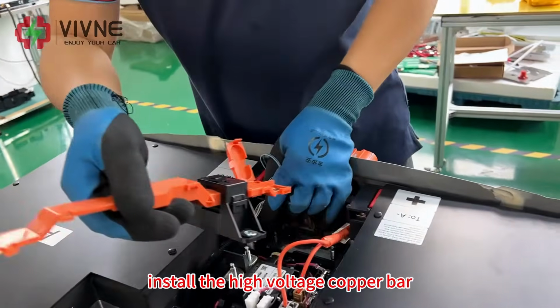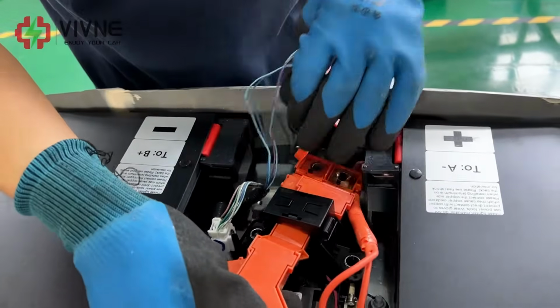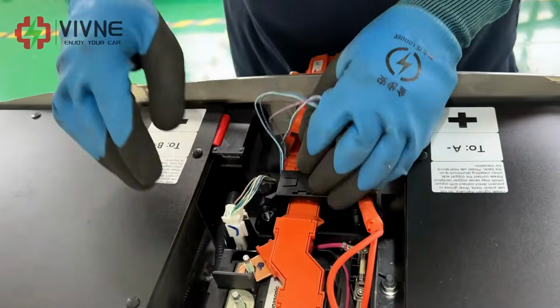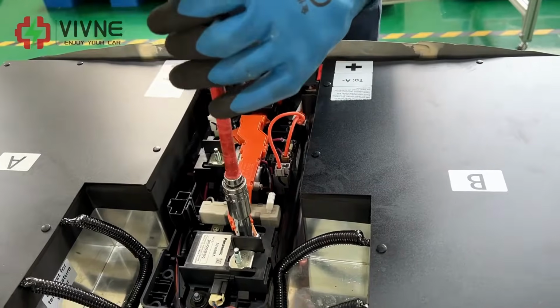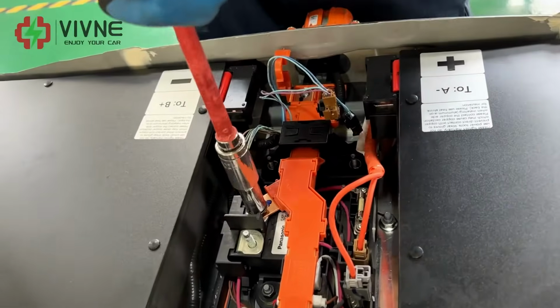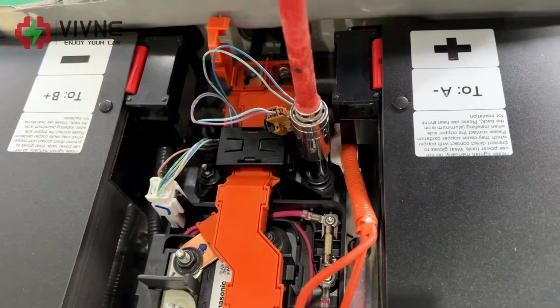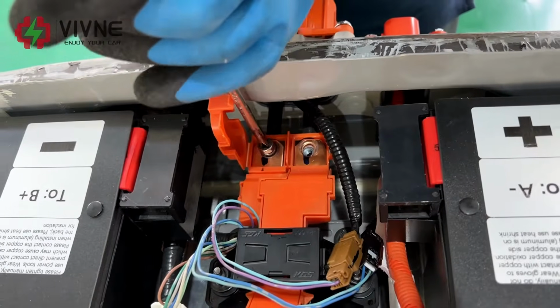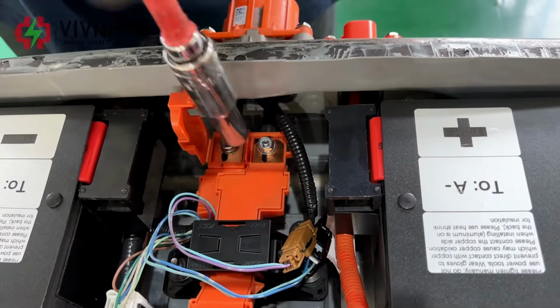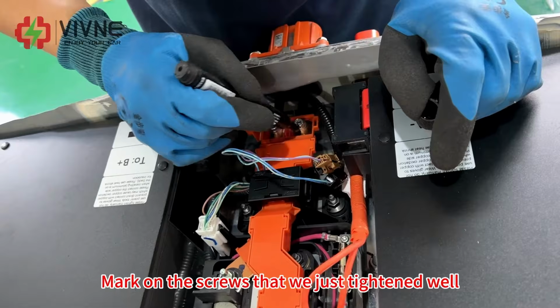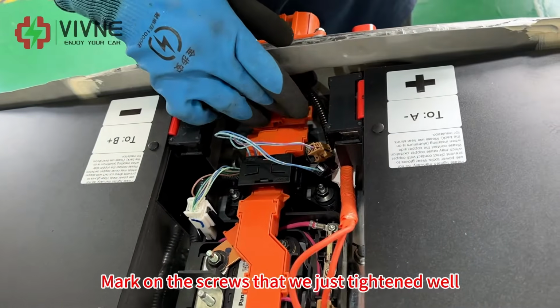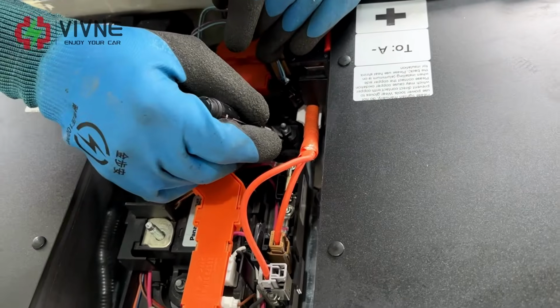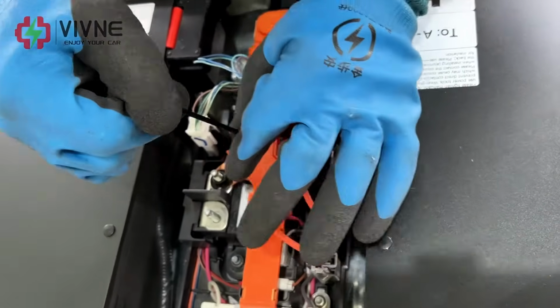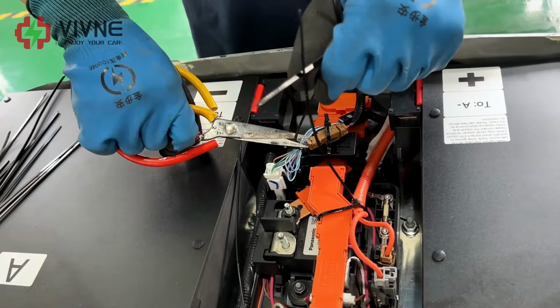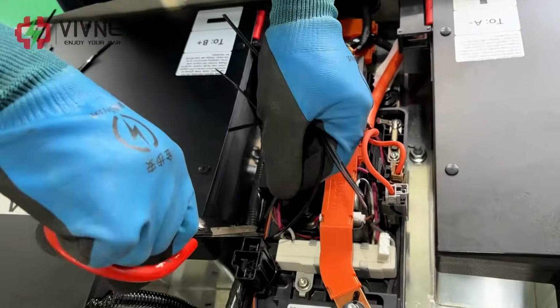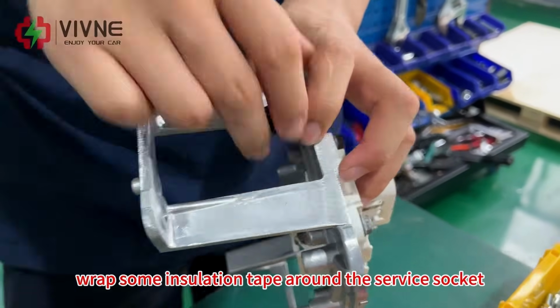Install the high voltage copper bar. Fix the copper bar. Mark on the screws that we just tightened well. Organize the cable. Wrap some insulation tape around the service socket.